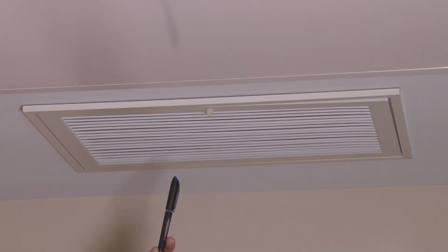In terms of maintenance by building staff, the only thing really that they need to get involved in is the filter. I would check to see how quickly the filter loads, but there is a return air grill right here. There's a little nylon screw that you back off, and on the back side of this return air grill is a filter media. That filter media stops any debris from going through the fan coil, loading up on the fan blades and or the coils. And it keeps things a little cleaner, less dusty in the suite. That will need replacing. Typical replacement under normal circumstances is usually quarterly, but with these types of buildings and multi-suite applications, that could be annually, if not at all, because there's very little debris or dirt, because everything that's coming into the building with makeup air is filtered, okay? And in terms of maintenance, other than that, there's really nothing to worry about.